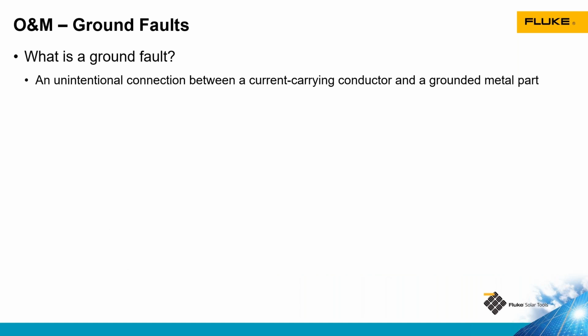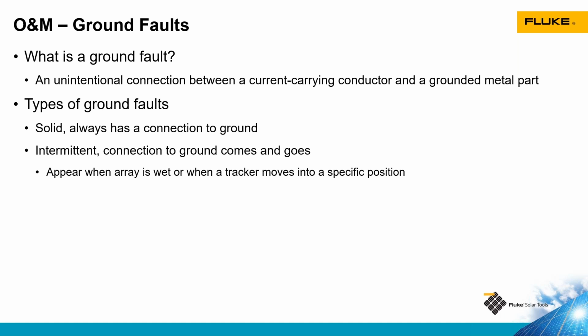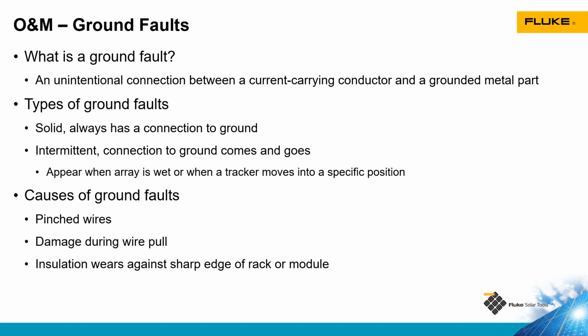Now, another common problem in the solar industry is ground fault. A ground fault is an unintentional connection between a current carrying conductor and a grounded metal part. There are two main types of ground faults: a solid ground fault, which is a low resistance connection that is always present. The second type is an intermittent ground fault that comes and goes based on the conditions on site. They could show up when it's wet out. It could be that it's getting pinched by a tracker at a certain time of day, or maybe when it's windy, the wire bangs into the metal array, the metal racking, and becomes grounded.